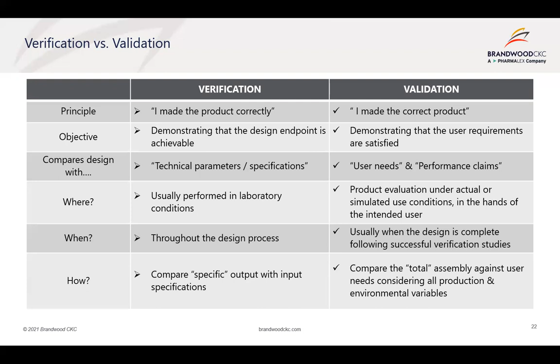On the other hand, validation is really about the perspective from the end user. So this is to verify that you've made the correct product as opposed to you've made the product correctly. So you'll be really demonstrating that the user requirements have been satisfied, that your claims are substantiated, and generally that involves product evaluation under actual or simulated use conditions, as if you were representing the final use of the product once released.